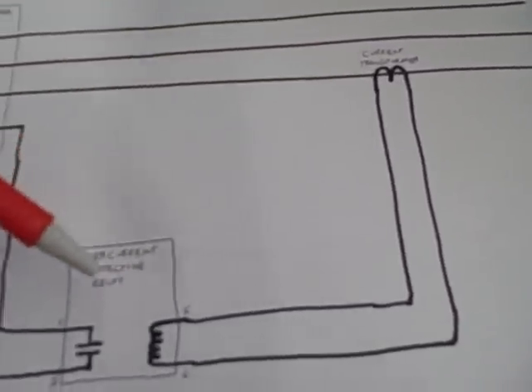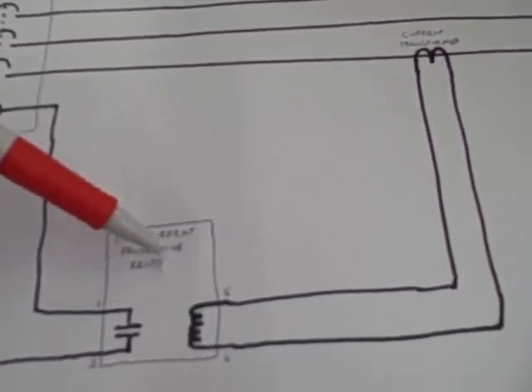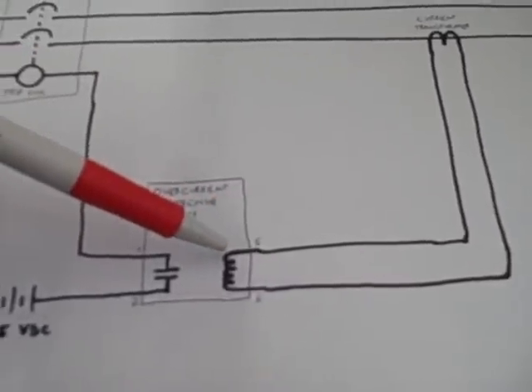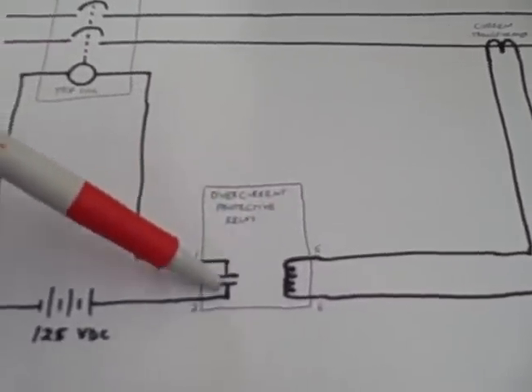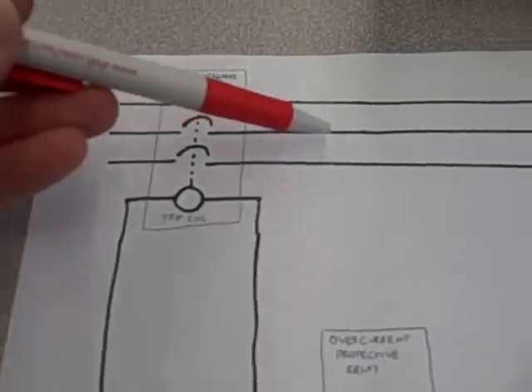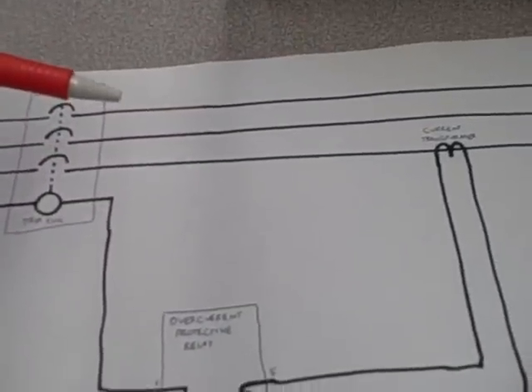But I'm just showing you this one protective relay for simplicity, monitoring current on one of the phase wires, and if that current becomes excessive, the relay closes a contact, sending trip power to the breaker to tell the breaker to open and to interrupt the three-phase power to the power lines.